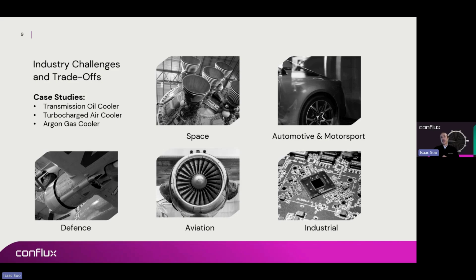So we need to design a part that's not only high performance and low pressure drop. We might also experience really tough fluids, and so fouling and the fouling build-up over 24/7 operation can be a factor. Now, we might oversize or upsize our parts to really help promote serviceability, cleanability, and account for that fouling factor as well.